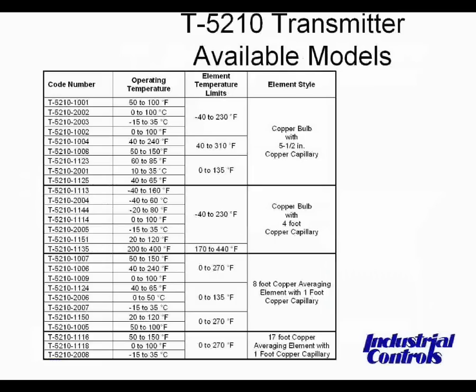The spans of 50, 100, and 200 degrees relate to how sensitive the specific transmitter is, and are used in the calculation along with the throttling range to determine what's called the proportional band, which is used to calibrate the controller. When calibrating a controller, we're not so much looking at the high and low temperatures, but rather the difference between them. In the first case, 100 minus 50 equals 50 degrees — that's the span of the transmitter.